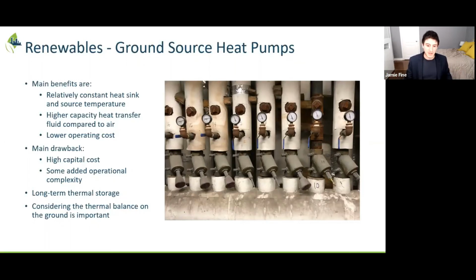So during the summertime, when you have a cooling load in your building, you're going to take heat from your building and put it in the ground. During the wintertime, when you have a heating load in your building, you take heat out of the ground, put it in your building. The main benefit is that temperature should remain relatively constant as long as the system is balanced. So you want heat being added and heat being removed to be fairly balanced with each other.